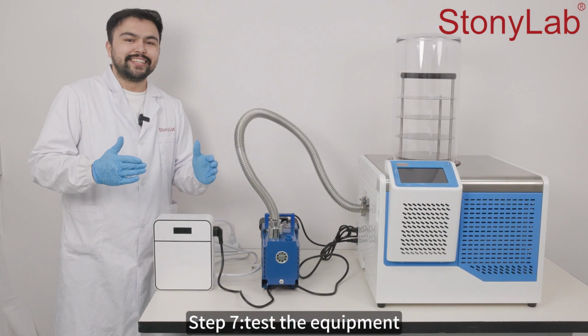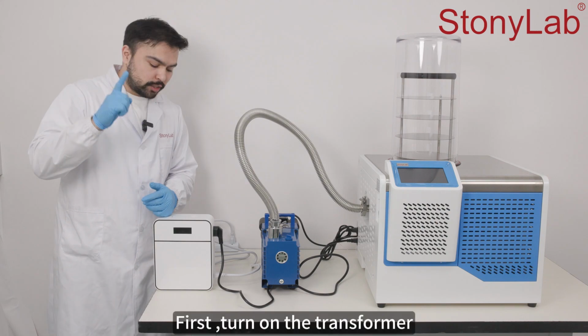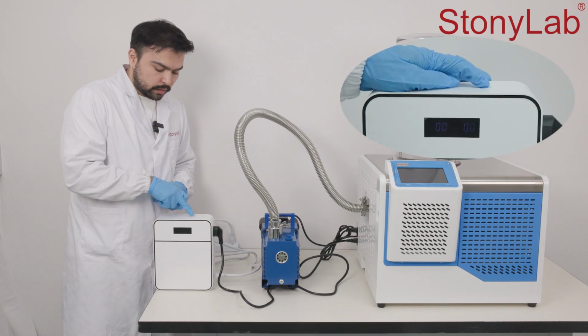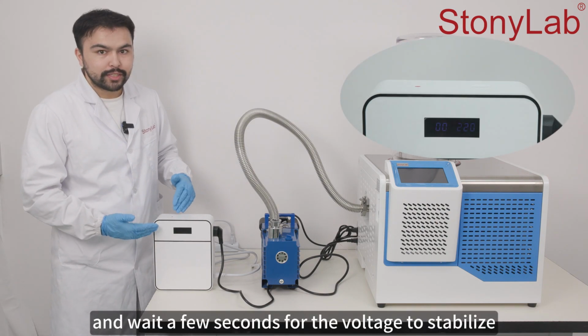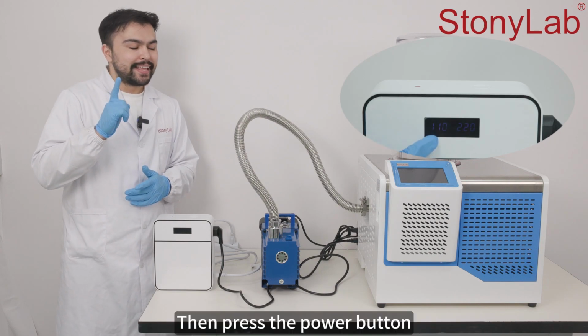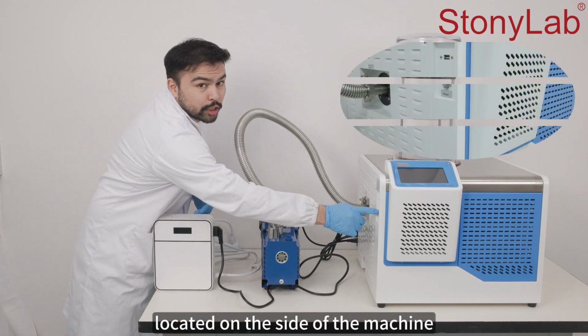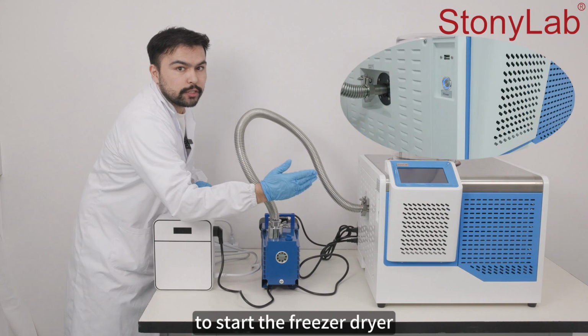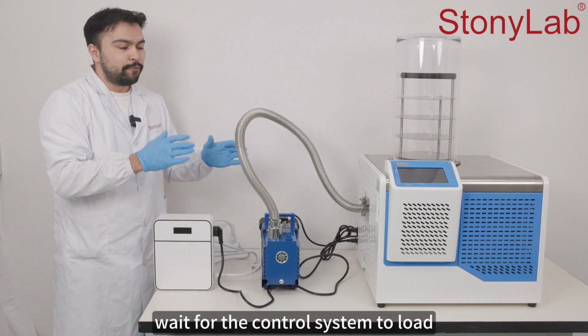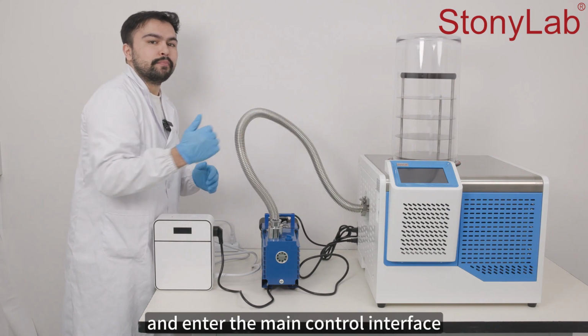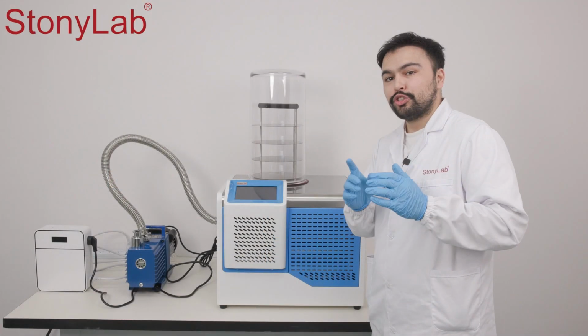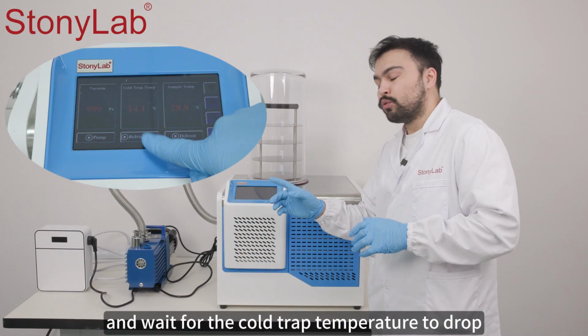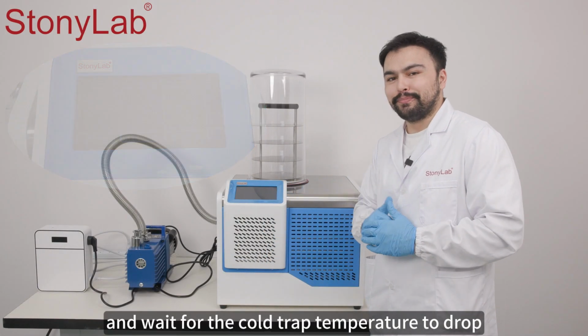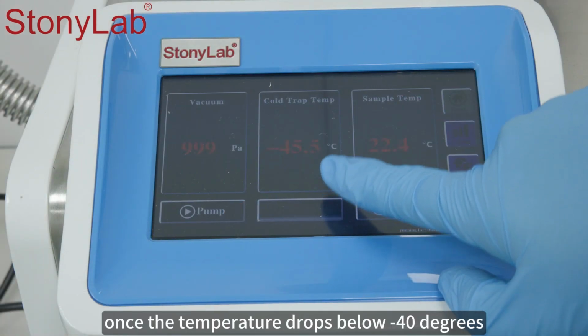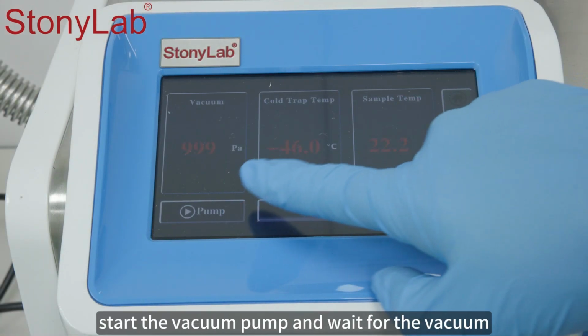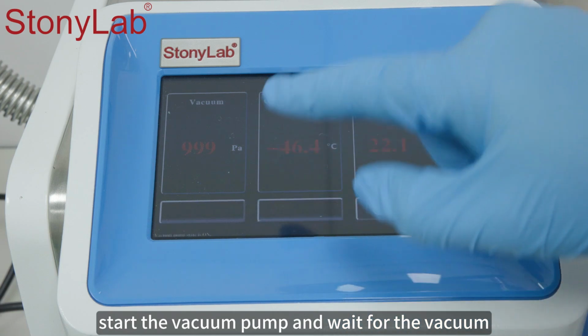Step 7. Test the equipment. First, turn on the transformer and wait a few seconds for the voltage to stabilize. Then, press the power button located on the side of the machine to start the freeze dryer. Wait for the control system to load and enter the main control interface. Turn on the refrigeration function and wait for the cold trap temperature to drop. Once the temperature drops below -40 degrees, start the vacuum pump and wait for the vacuum.